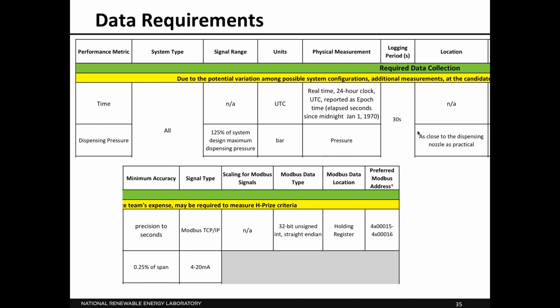contestant's PLC to report to us time based on a 24-hour clock measured in UTC in epoch time every second, in precision in seconds. We'll only poll you every 30 seconds, but we need the precision to be in each second. So when you see here the signal type listed as Modbus TCP/IP, that means that's a non-isolated signal and will come to us via your PLC. I also give you some Modbus data types. This particular one requires 2 holding registers because it's a 32-bit integer, and holding registers in Modbus are only 16 bits long, so we need 2 of them.